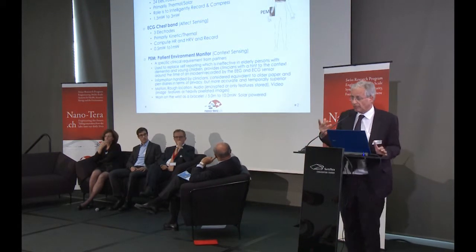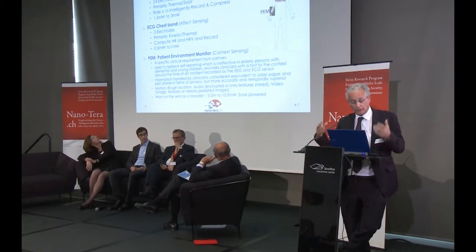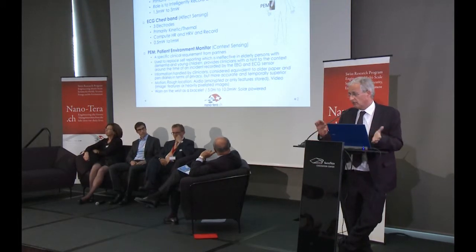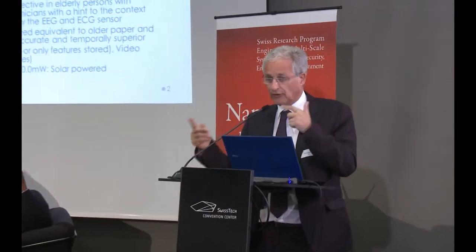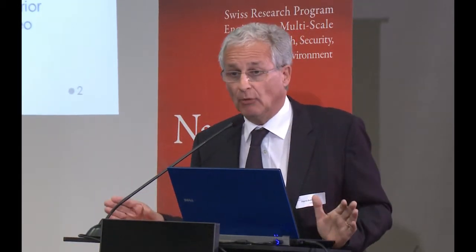What is the idea? To have wearables. We would like for epilepsy and for Alzheimer to have an electroencephalogram baseball cap for the brain sensing of the sensor. And we would like to obtain only 24 electrodes and with a sample rate of 500 to 1,000 samples per second. And the energy there will be either solar, or both solar and thermal, thermoelectric generators. And the role is to intelligently record and compress the data sensed by the EEG cap. The power budget is roughly 3 milliwatts.